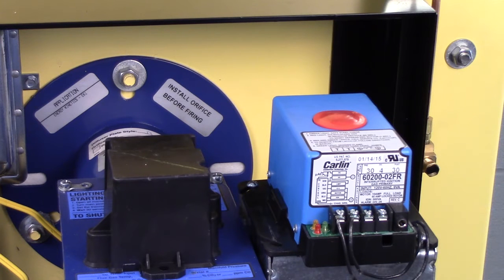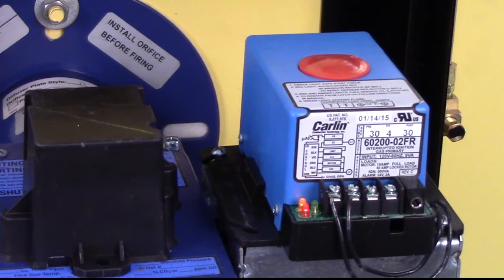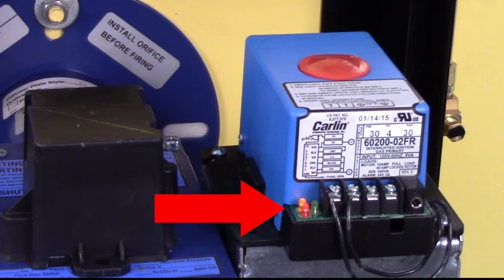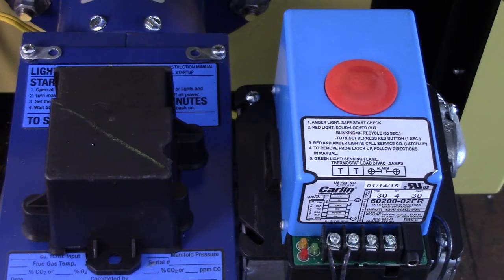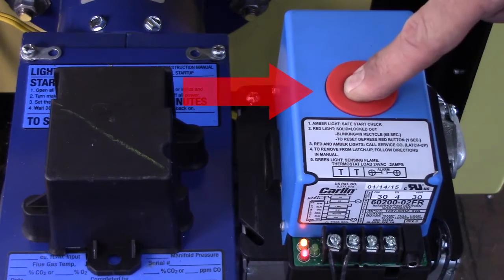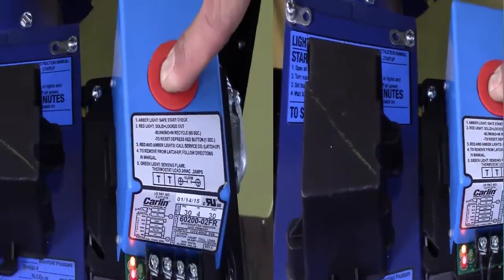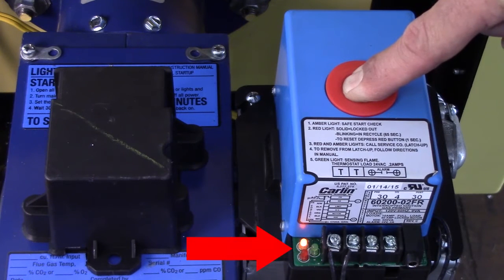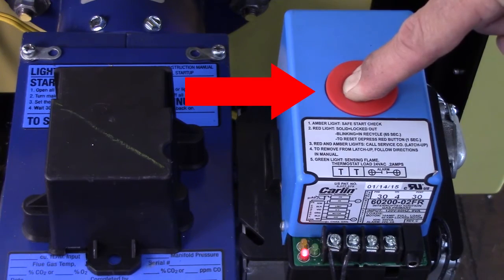The problem that caused the burner lockout must be corrected before returning the burner to normal operation. If the primary control is in latch-up, the red and amber LEDs will both be on. The control enters latch-up if a lockout occurs 3 times on the same call. To reset, press and hold the red reset button down without releasing. After about 10 seconds, the red and amber LEDs will begin flashing alternately. Continue holding the reset button down for about another 20 seconds.